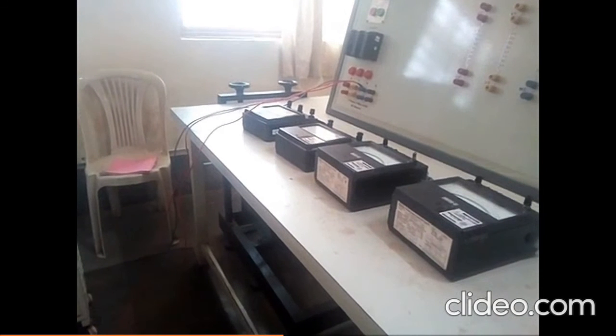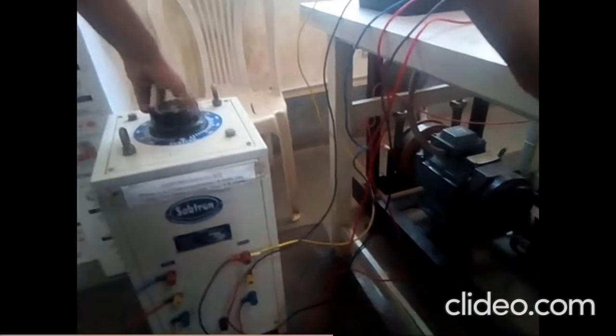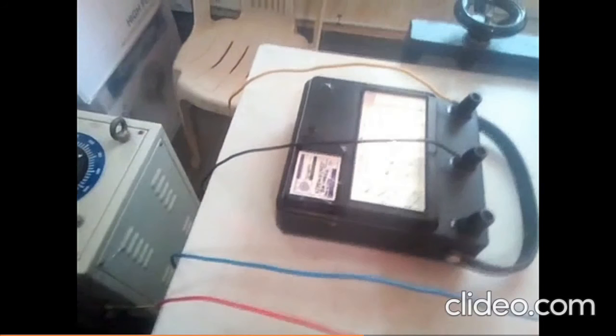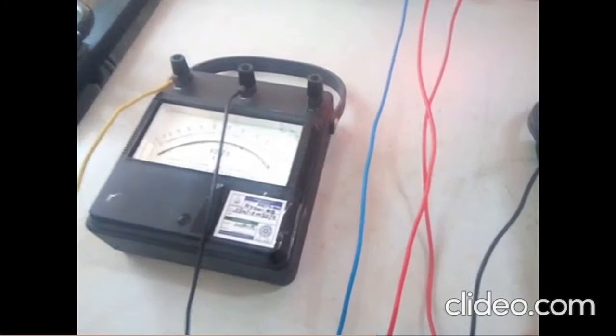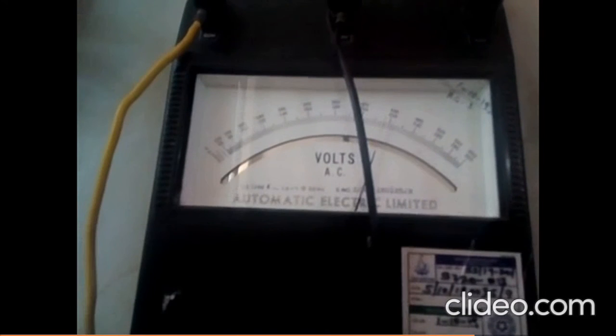You can see the meters used for conducting the no load test. Further, we make the connections as per the circuit diagram. The first step is to switch on the main supply, that is the three-phase supply. After that, using the three-phase auto transformer, which acts as a starter, we slowly apply the input voltage to the three-phase induction motor step by step. We observe the applied voltage on the voltmeter. The rated voltage of the induction motor is 415 V, and for the no load test we need to apply 415 V to the motor, as you can observe here.